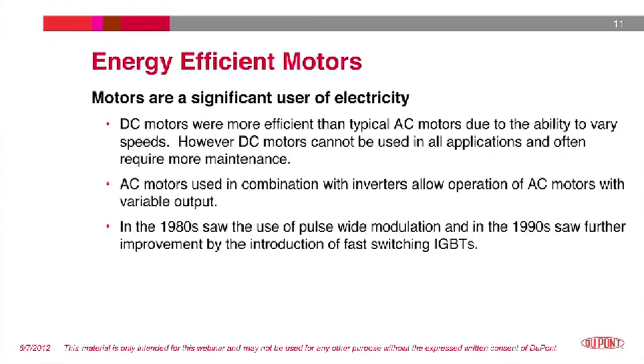The ability of a DC motor to be operated at variable speeds enabled more efficient operation than AC motors. However, DC motors cannot be applied in all motor applications, and the maintenance of DC motors is more involved. As a result, the use of inverters became the method of allowing AC motors to be operated at variable speeds, capturing the benefit of variable speed operation without the cost of maintenance of DC motors. In the 80s, pulse width modulation was adopted as the preferred method to provide the AC output from the inverter.